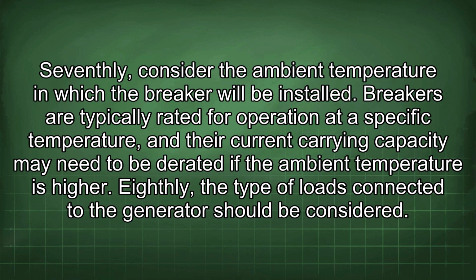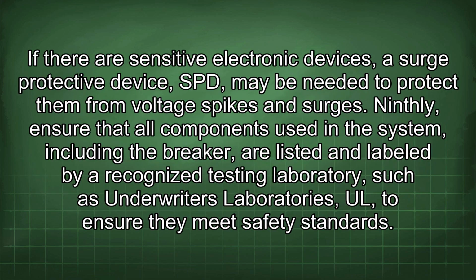Eighthly, the type of loads connected to the generator should be considered. If there are sensitive electronic devices, a surge protective device, SPD, may be needed to protect them from voltage spikes and surges. Ninthly, ensure that all components used in the system, including the breaker, are listed and labeled by a recognized testing laboratory such as Underwriters Laboratories, UL, to ensure they meet safety standards.